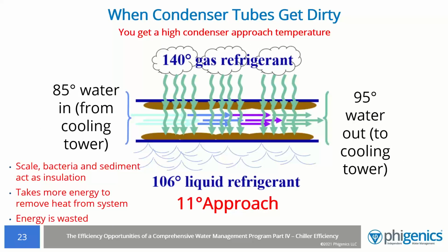Now we take a situation where we've got a buildup in the tubes. And again, as Mike indicated, the number one issue we see in chillers all over the country, the most common problem, is high condenser approach, or tube fouling. And there's good reasons for that, because of your open air wash system cooling tower. With these systems, there's a lot of opportunity for fouling. It can come from scale, bacteria, sediment, microbiological fouling.